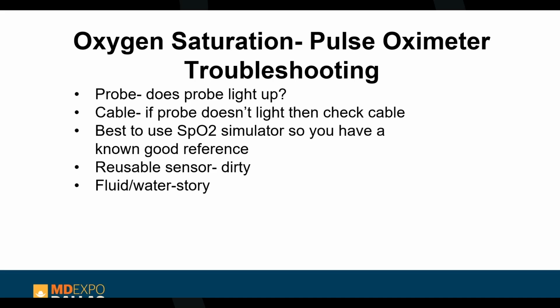I had this pulse oximeter probe that I was checking out, and every time I kept getting SPO2 malfunction. It was on a Philips monitor on an X3. I'd unplug it, restart the monitor, wait for everything to come up, plug in that cable, and it went immediately to SPO2 malfunction. Like, man, what's going on with this thing? It's a bad cable. I didn't even have the sensor plugged in.